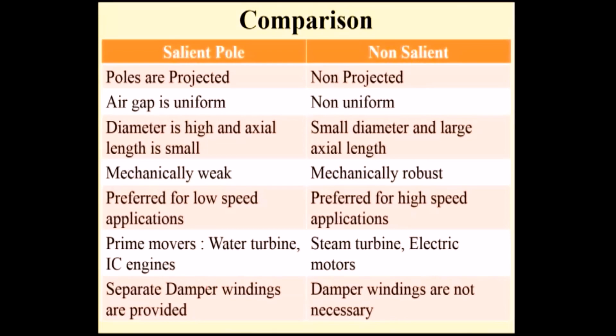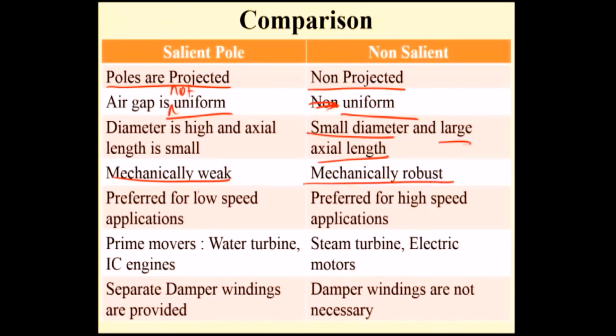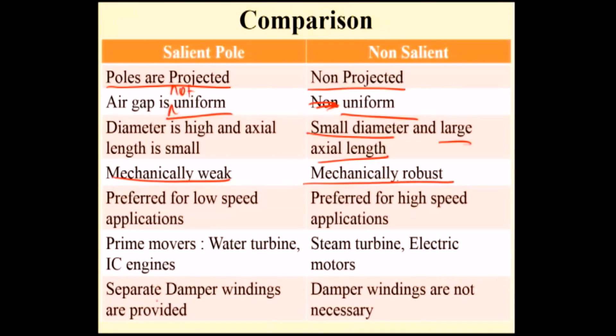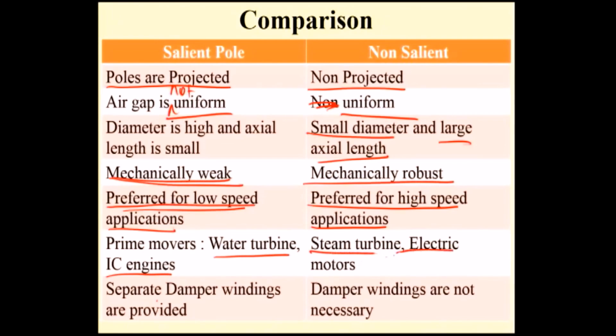Comparing both rotors: the salient pole rotor has projected poles, non-uniform air gap, large diameter, small axial length, and is mechanically weak — making it suitable only for low-speed applications. The non-salient pole rotor has non-projected poles, uniform air gap, small diameter, large axial length, and is mechanically robust — suitable for high-speed applications. Low-speed prime movers such as water turbines and IC engines are used with salient pole rotors, while steam turbines and electric motors are used with non-salient pole rotors. Damper windings are required for salient pole rotors but are not necessary for non-salient pole rotors.